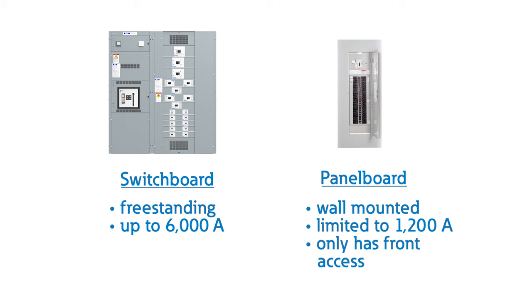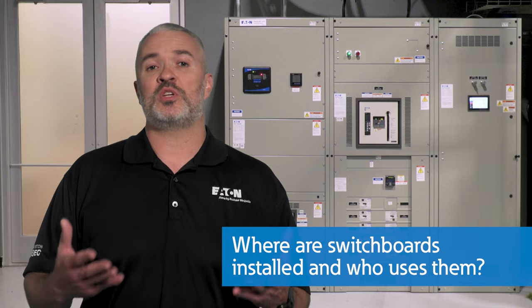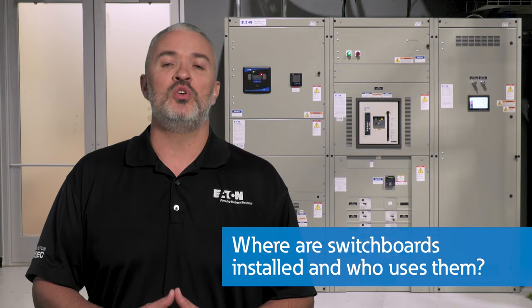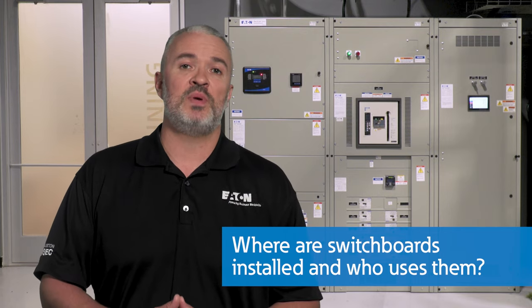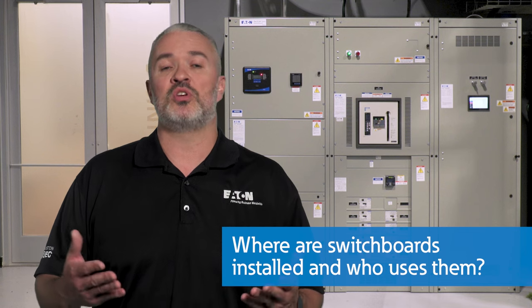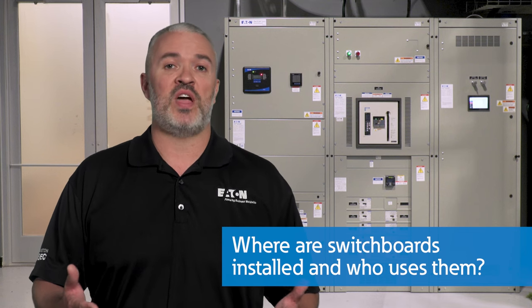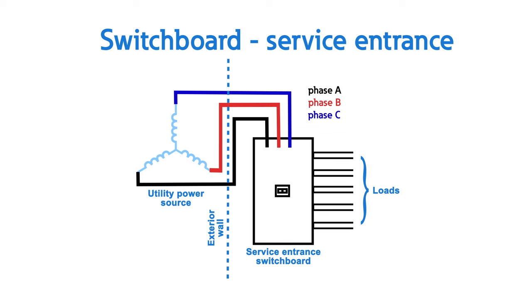Similar to panel boards, switchboards can be front-connected, requiring only front access. However, switchboards can allow rear access if desired. Switchboards are key pieces of low-voltage distribution equipment. They can either be fed from a power circuit breaker and upstream switchgear assembly, or fed directly from the electric utility service transformer in smaller facilities, which is referred to as service entrance.